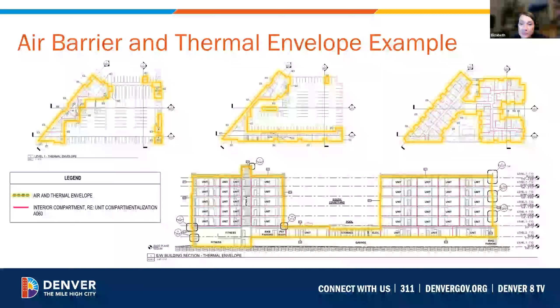Let's look at HVAC and kitchen next. Many of the ASHRAE requirements are identical to the IECC. HVAC control requirements for some systems and parking garage ventilation controls have some slight differences, so teams will want to review those sections, as well as the Denver Mechanical Code more specifically. But you'll find that a lot of things still align. Duct testing is also just slightly different. Testing is required for ducts operating at 3 inches of static or greater for both IECC and ASHRAE. But ASHRAE also adds testing for all outdoor ductwork. And these instructions must be noted in drawings to flag for the contractor.